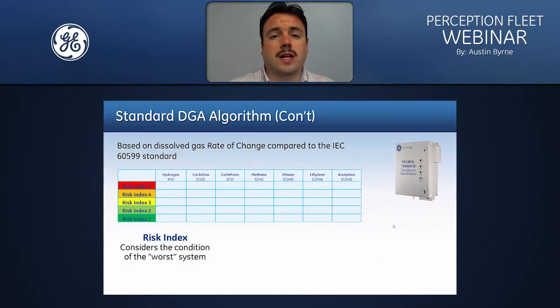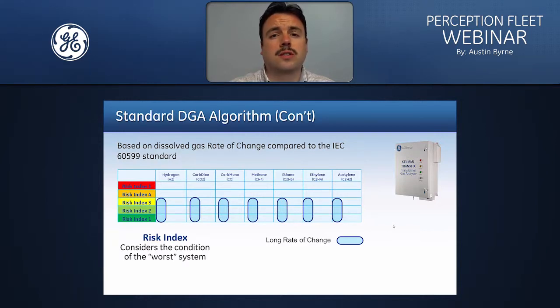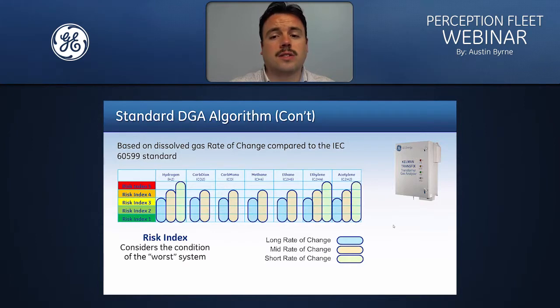Another thing that we look at within the DGA algorithm is the gas rate of change, and that is in comparison to IEC 60599, which specifies the gas rate of change in an expected normally operating transformer. Again, you can see the different types of rate of change and what risk index they can indicate. So we look at 3 different time spans within the asset: a long rate of change, a mid rate of change, and a short rate of change. You can see for hydrogen, ethylene and acetylene, we look at short rate of change, and the short rate of change can push the asset into a risk index of 5, whereas for carbon dioxide, carbon monoxide, methane and ethane, the highest risk index that they can reach is a mid rate of change, pushing the asset into a risk index of 4.